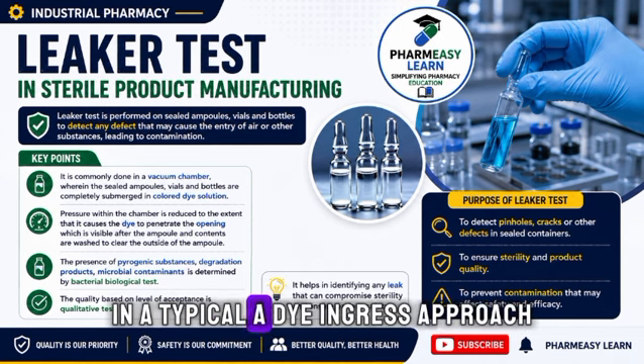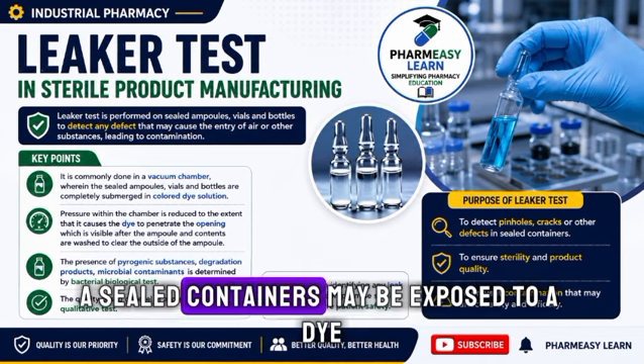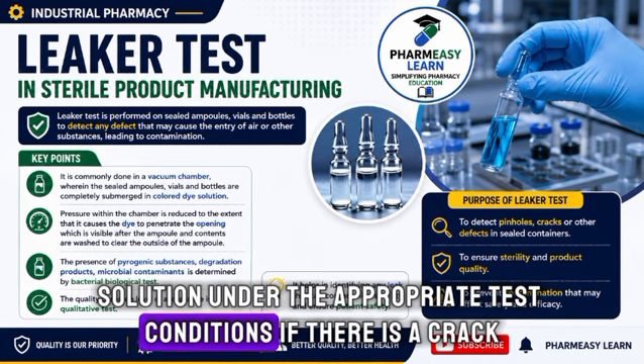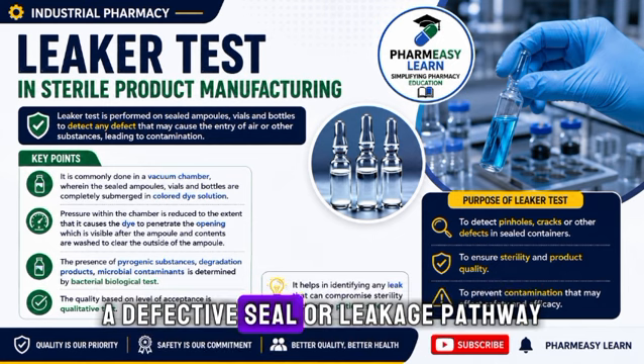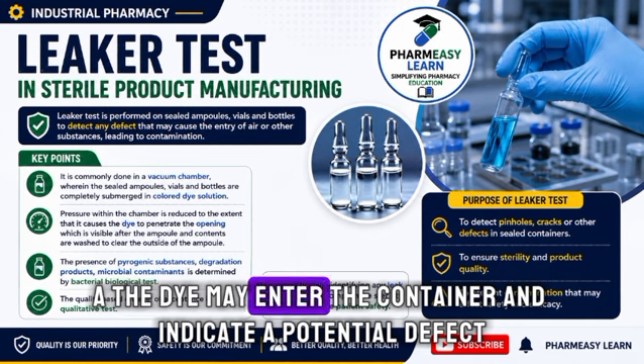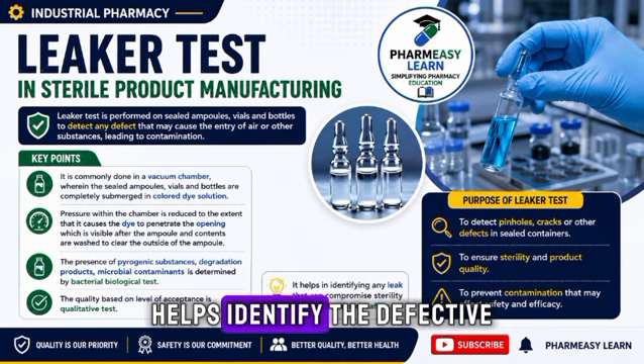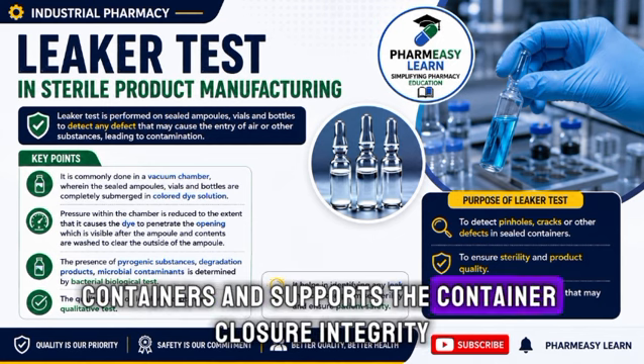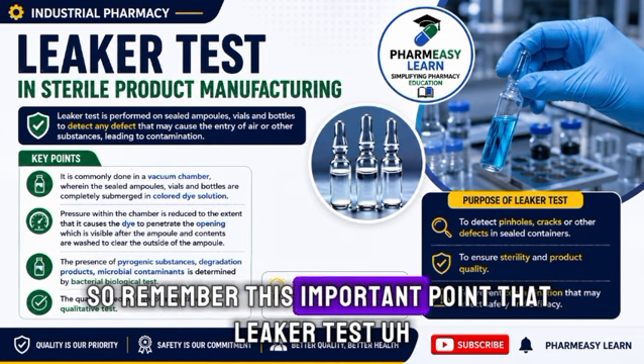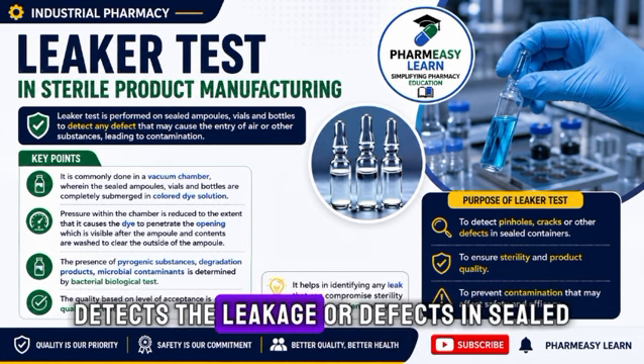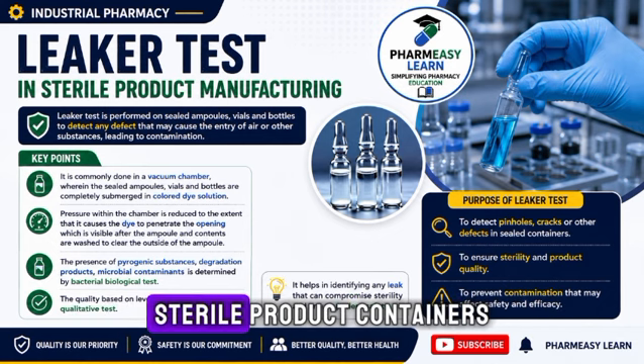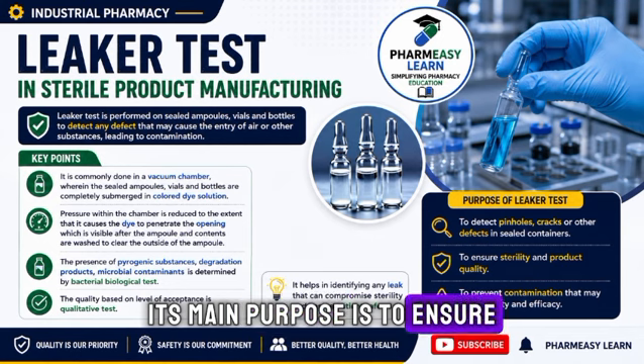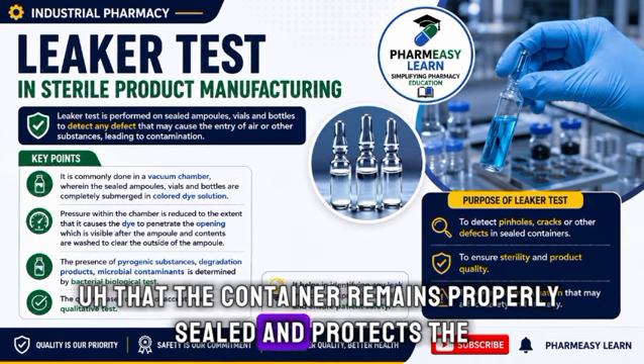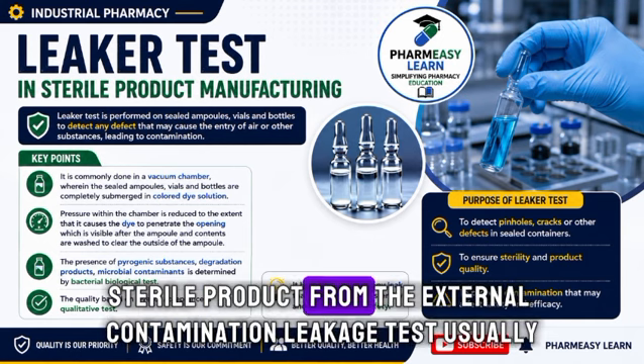In a typical dye ingress approach, sealed containers may be exposed to a dye solution under appropriate test conditions. If there is a crack, defective seal, or leakage pathway, the dye may enter the container and indicate a potential defect. Therefore, the leaker test helps identify the defective containers and supports the container closure integrity. So remember this important point that the leaker test detects leakage or defects in sealed sterile product containers.